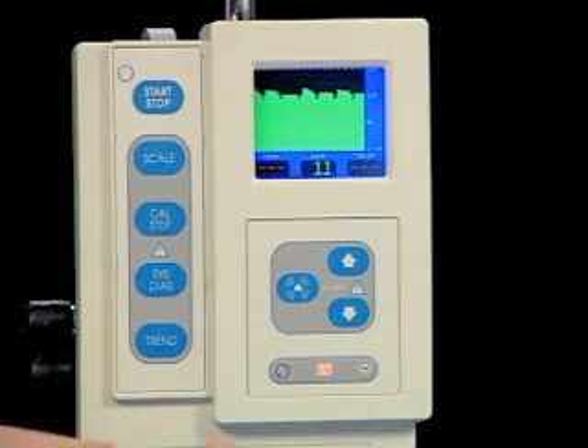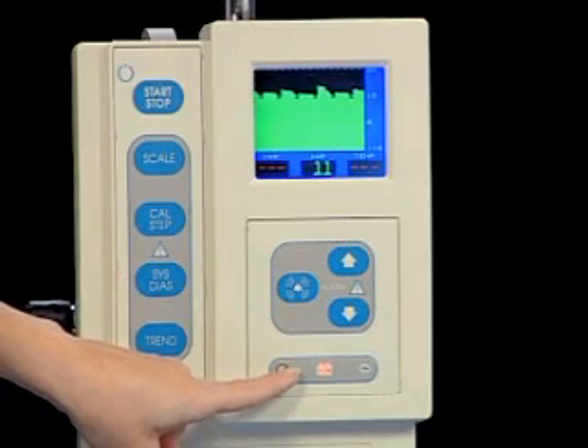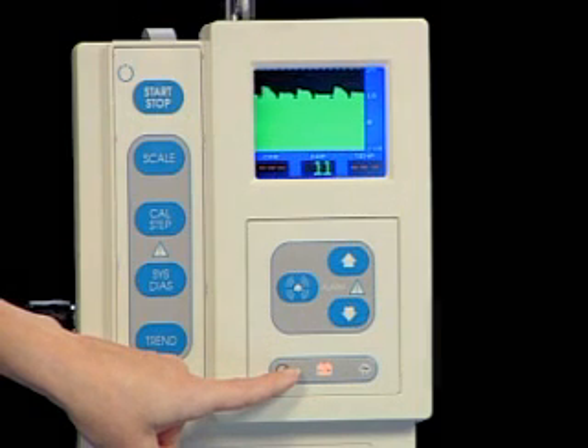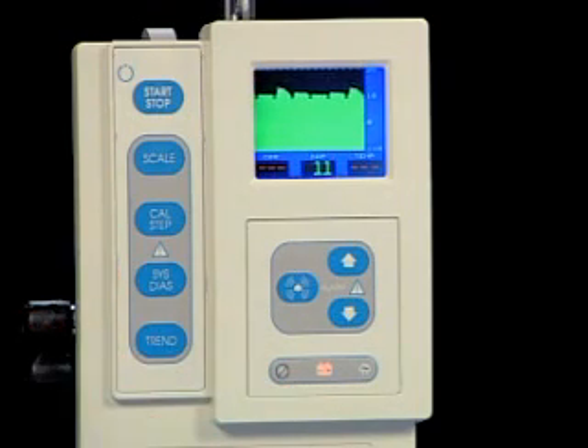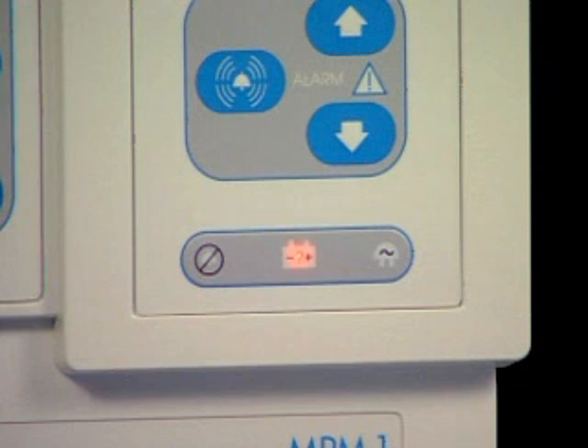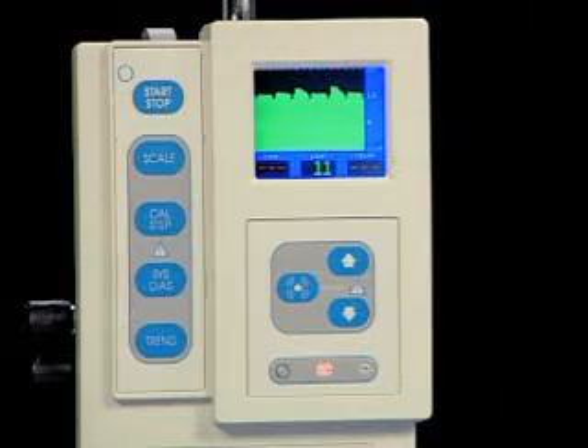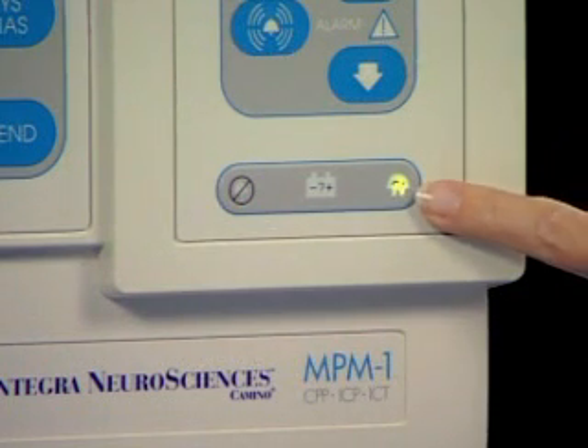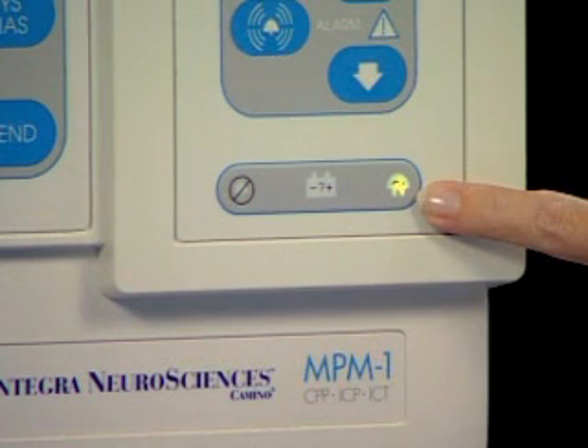The low battery indicator illuminates when the MPM-1 is operating on battery power and less than 15 minutes of battery power remain. If illuminated, connect to AC power as soon as possible to prevent the loss of trend data. If the battery completely discharges, all stored trend data will be lost. The AC power indicator illuminates when connected to AC power. The battery will charge when this is illuminated.